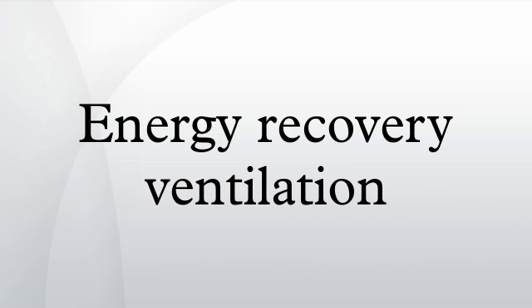In new construction situations, energy recovery will effectively reduce the required heating and cooling capacity of the system. The percentage of the total energy saved will depend on the efficiency of the device and the latitude of the building. Due to the need to use multiple sections, fixed plate energy exchangers are often associated with high pressure drop and larger footprints. Due to their inability to offer a high amount of latent energy transfer, these systems also have a high chance for frosting in colder climates.